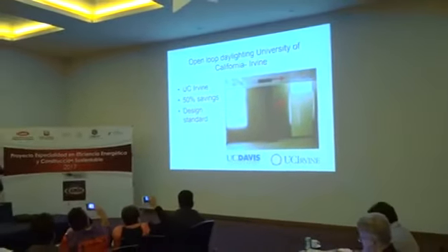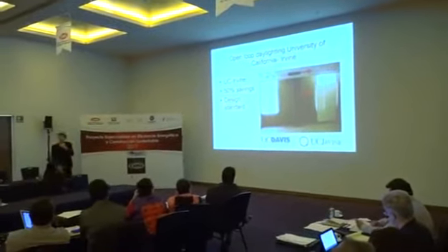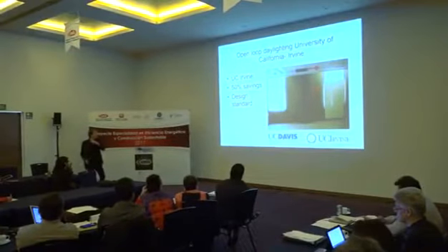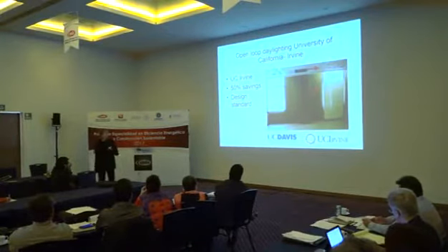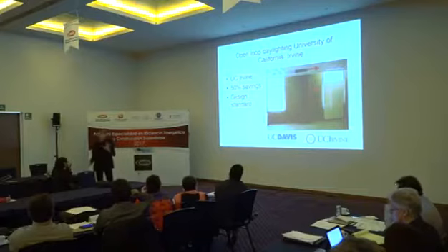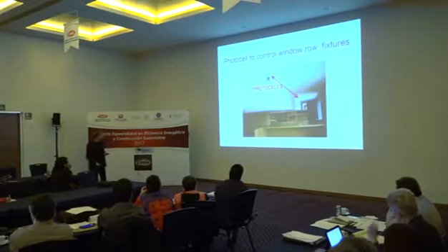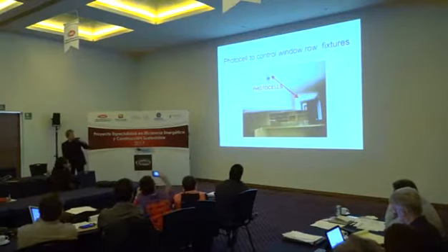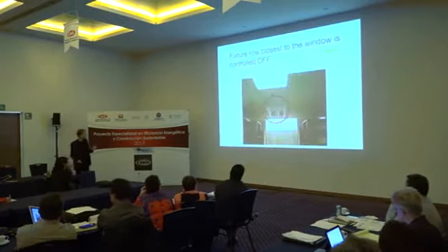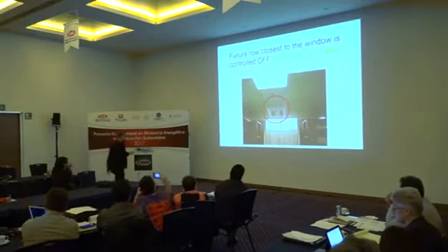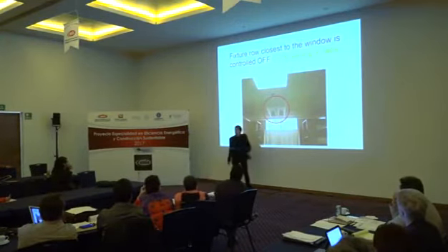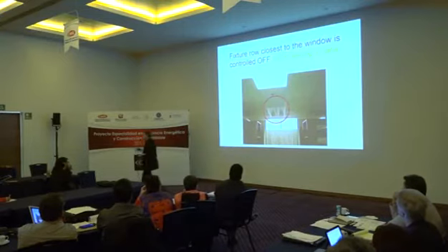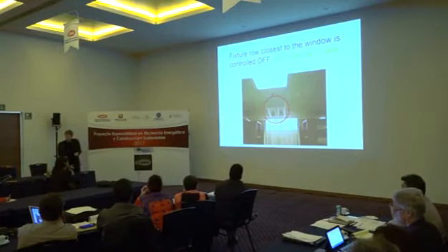I use this a lot in laboratory spaces, and we did a lot of daylighting design down at UC Irvine, and we made a decision that when there was light coming through the windows, we would turn off all the fixtures along the window wall. We just made that decision, and we tested it. This is what the sensor looks like. It's looking out, not looking at the desk. It's saying there's daylight, lights will go off. This was cheap and worked very well. It kept all the other fixtures on, but turned all of these off. This is a very easy, quick, very cheap way of doing daylighting.